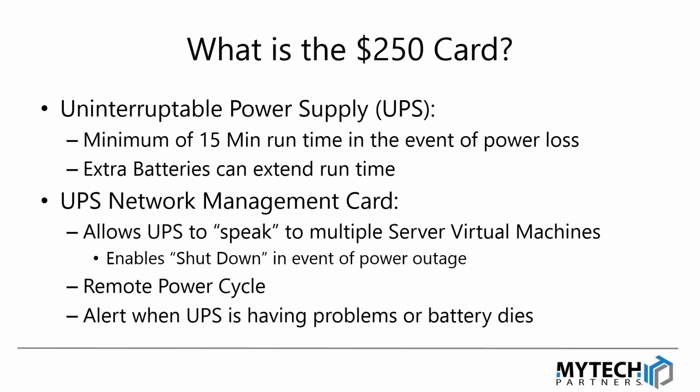The reason why is that it allows us to suffer through a short power outage that might only be a few minutes long, because sometimes power outages are just a bit of a brownout. So maybe just a little dip that'll keep you still up and running. You won't have to worry about it. Or if it does extend beyond 15 minutes, the UPS will have enough time to effectively shut down your servers. And that was one of the key variables. We want to have enough time to be able to shut down your servers.